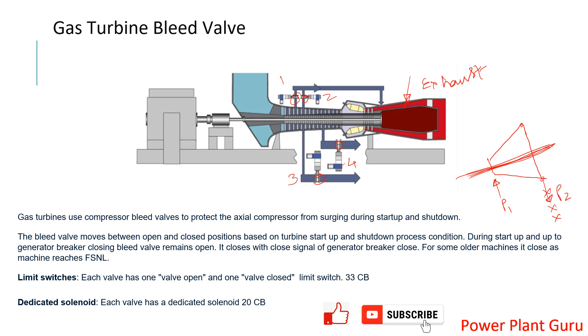The compressor is running at RPM but there is no exhaust. Pressure builds up, creating back pressure, and that pressure tries to push back. The pressure increases stage by stage, and once back pressure is very high, air starts coming back. That is the surging phenomenon, which is very dangerous for equipment to operate.